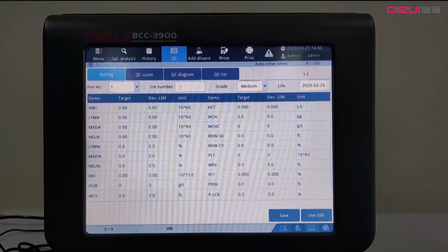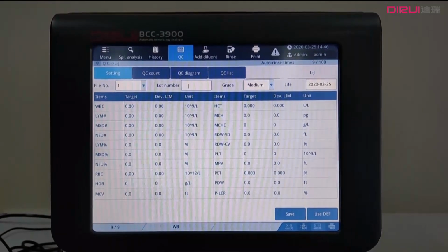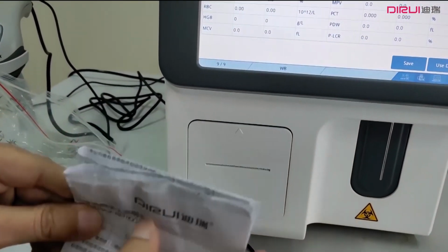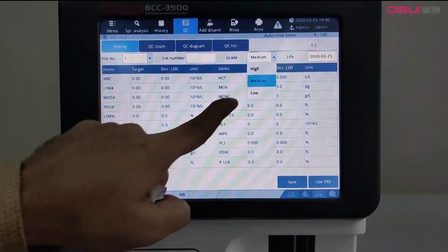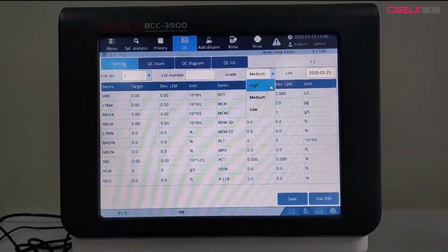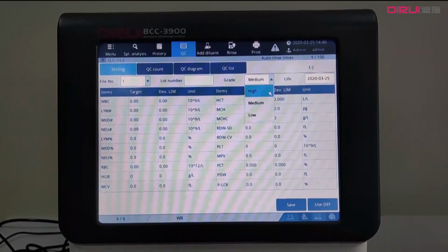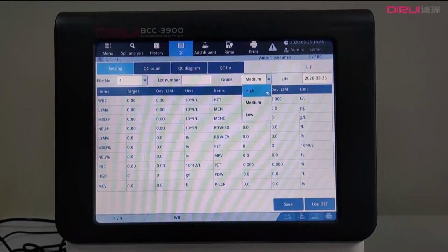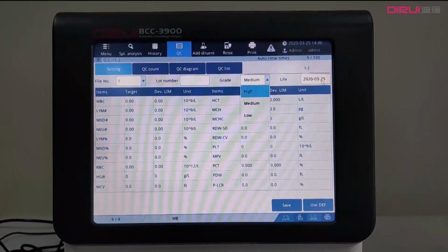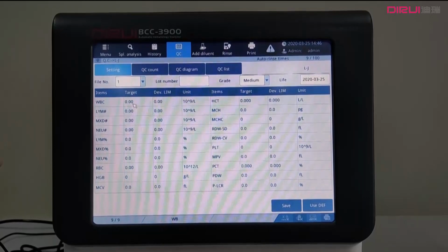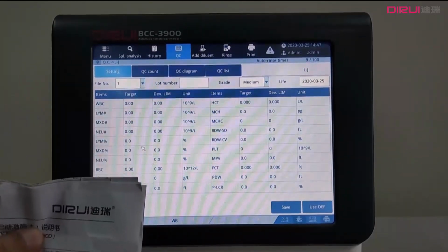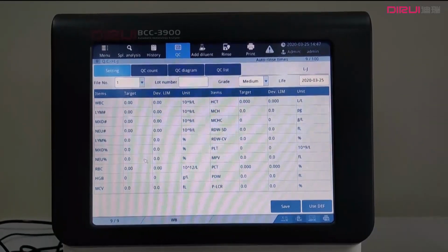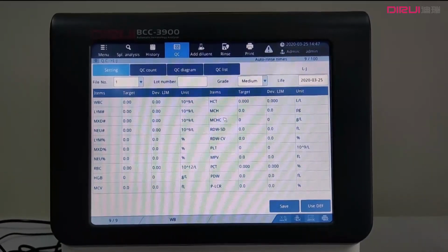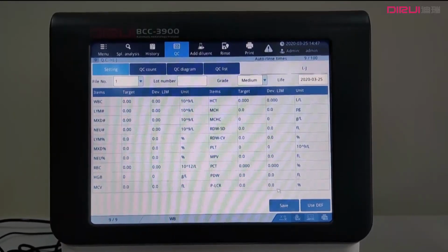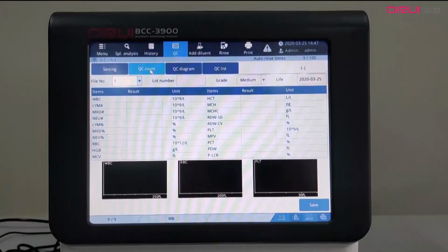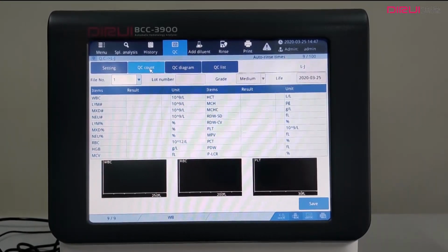When we open our QC box, inside it has all the lot number and grade information. Grade information means we have three different kinds of QC: medium, high and low. You can choose according to the reagent insert or according to your choice, and this is the expiry date. Then you need to input all the information from the reagent insert, all the information from this target, and save. After saving, go to QC count.